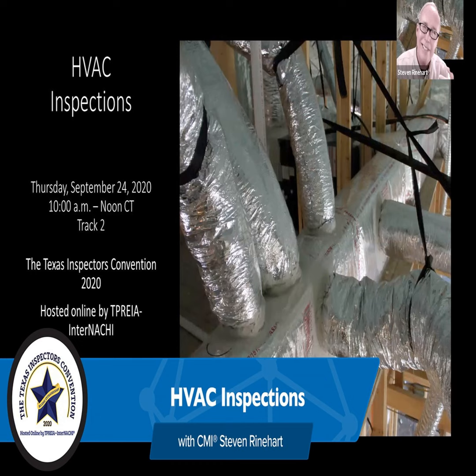Is there a set number? I'm not fixed on a number any more than I'm fixed on a number for cooling without some kind of sliding scale. I mean, there's a lot of reasons why it might not be as hot or cool, but for the most part, if you can get real close to the air handler, there's typically a register that is real close. You see the air handler and you think, oh, right on the other side, that's got to be a real short duct. So I'm getting it pretty close from the plenum. I would say if I didn't get 25, 30 degrees, I would be wondering if it's gas.